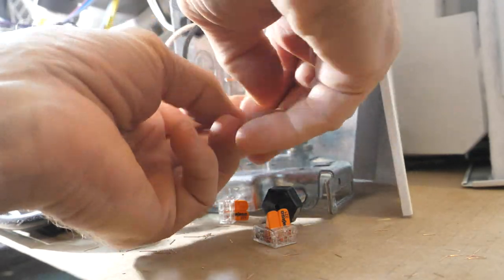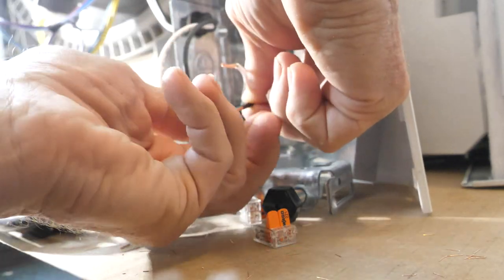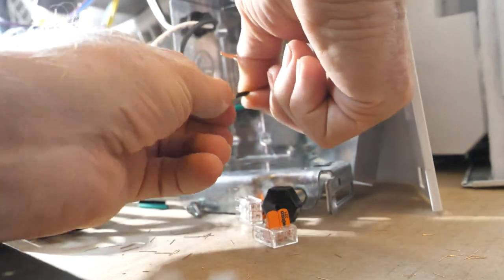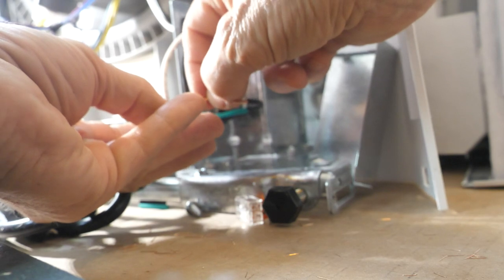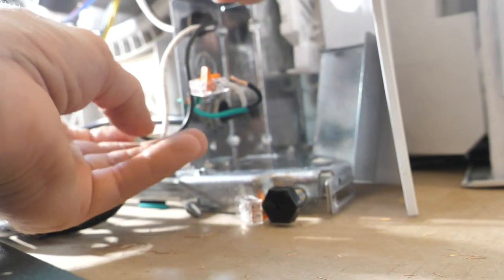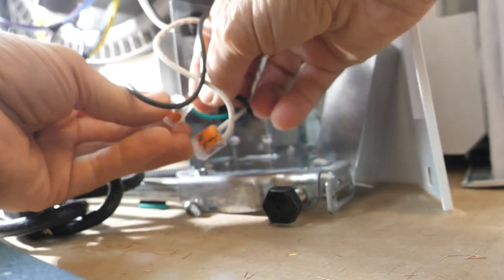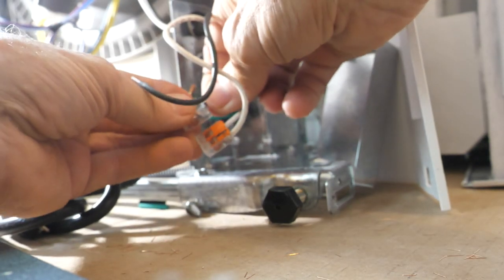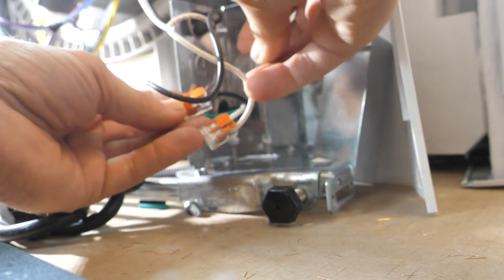Now we'll hook together the neutrals. First, twist the wires so that there aren't any loose strands of wire. Now use wire connectors to connect together the neutral wires. In this case, I'm using Wago lever nuts. Then connect together your black hot wires in the same manner.